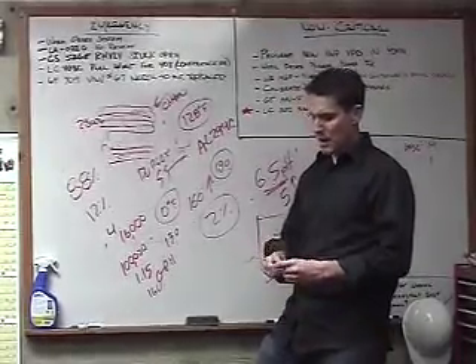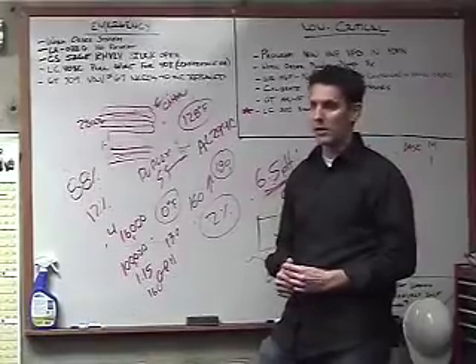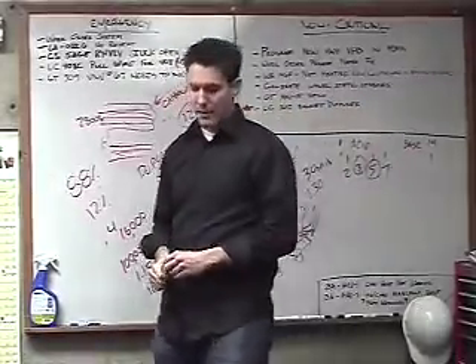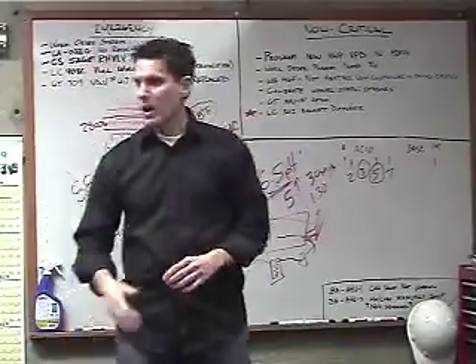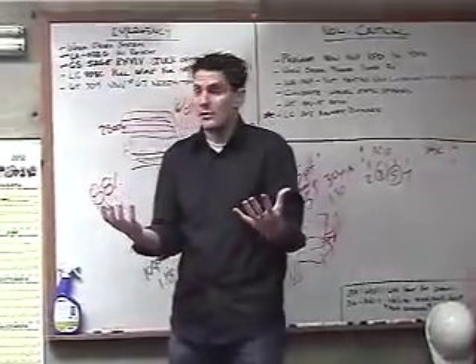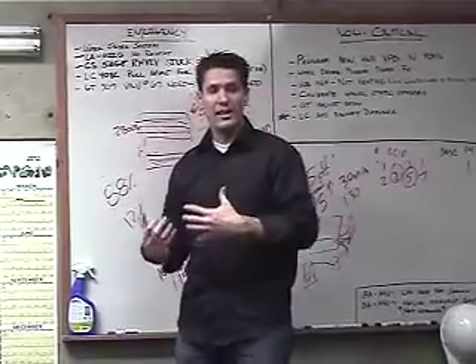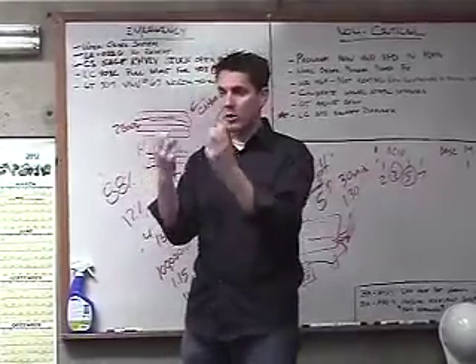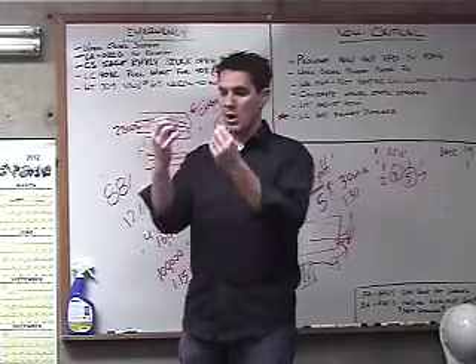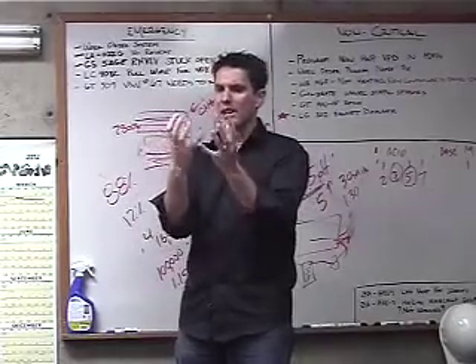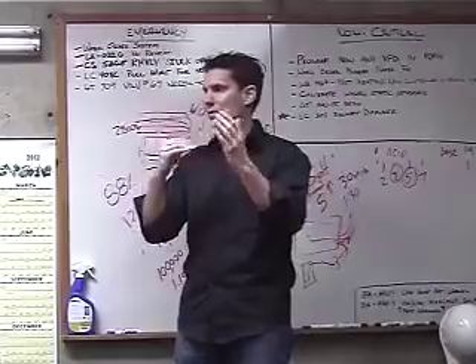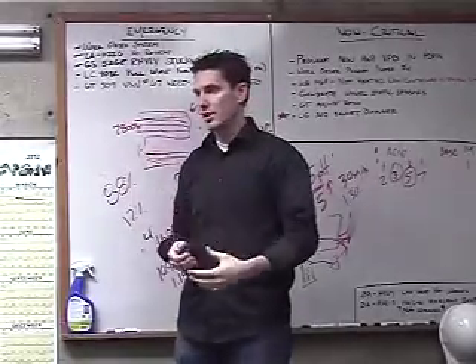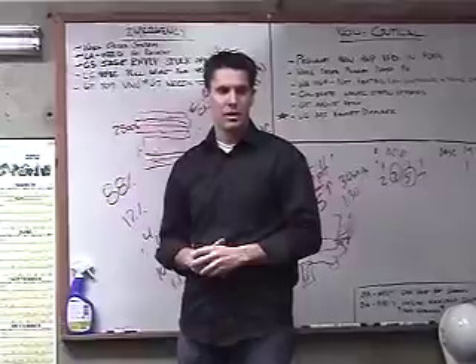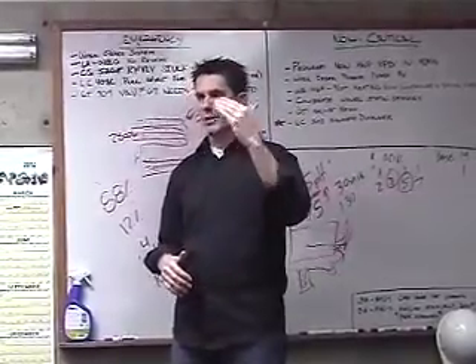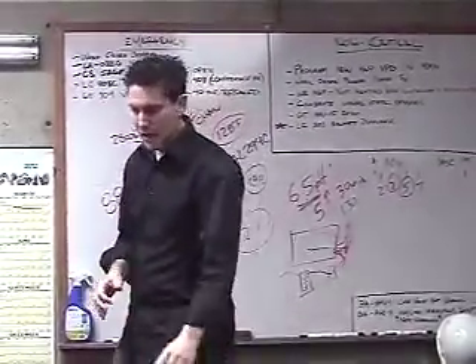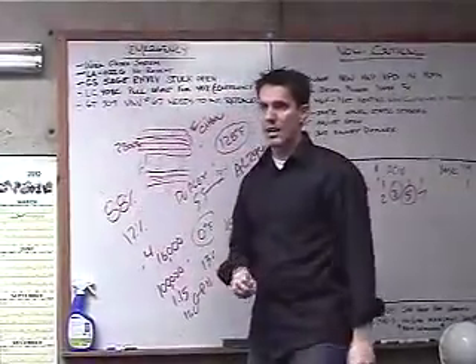That's one of the biggest issues that we see with condensing boilers: lack of maintenance. Unfortunately, condensing boilers require more maintenance because it's a dirtier environment. It's not the boiler's fault, it's the application. Every time you get water forming inside, you start to form rust, minerals, particulates, whatever, and it starts to block passageways inside your heat exchanger. It starts to eat up your heat exchanger, and that will quickly kill your boiler. So you need to make sure you're doing the regular maintenance that we're going to go over here. Any other questions on this before we start getting more into the technical side of the boilers?